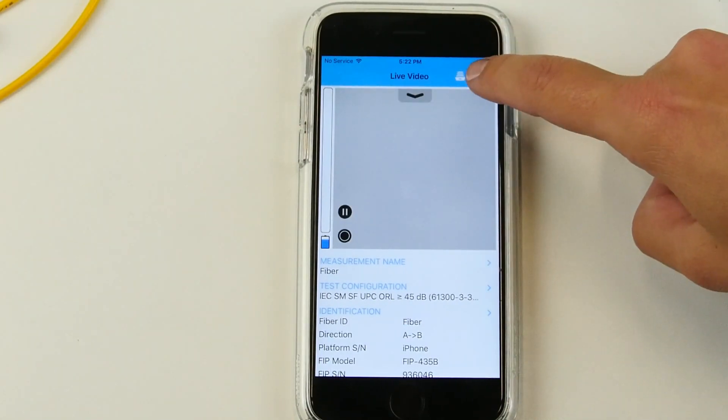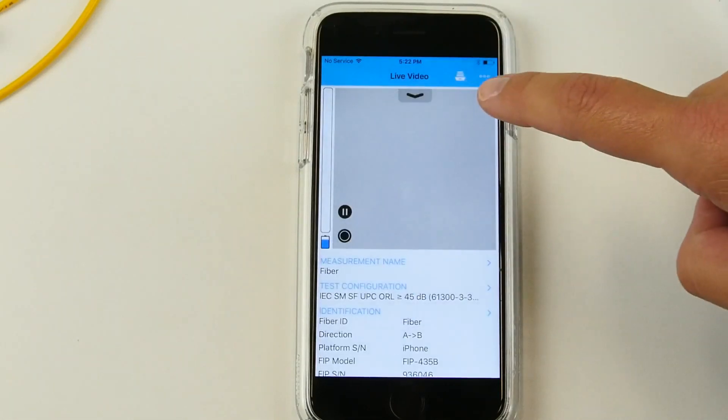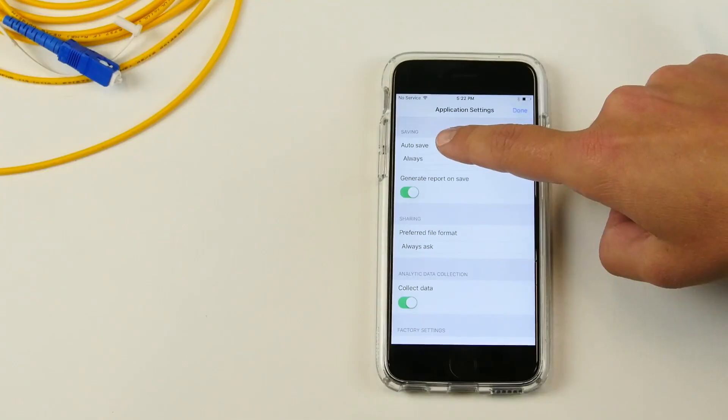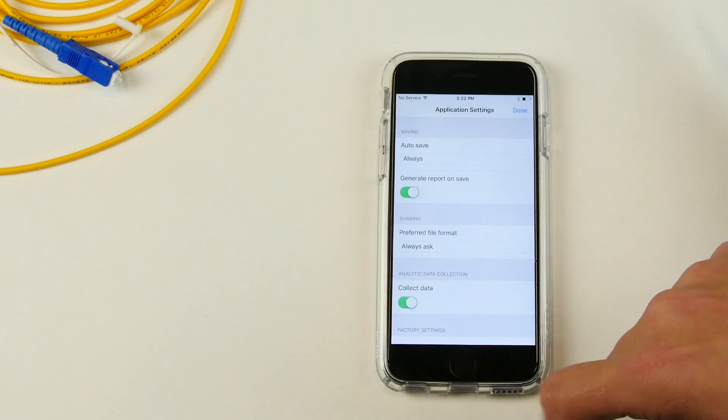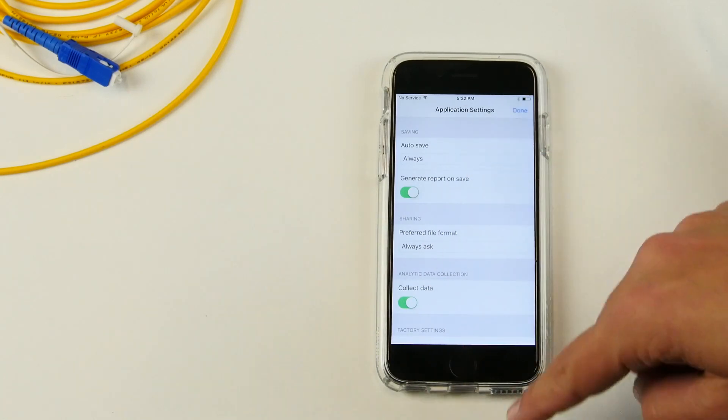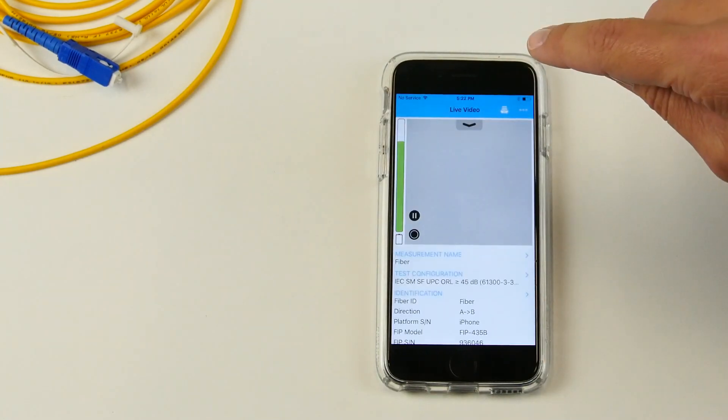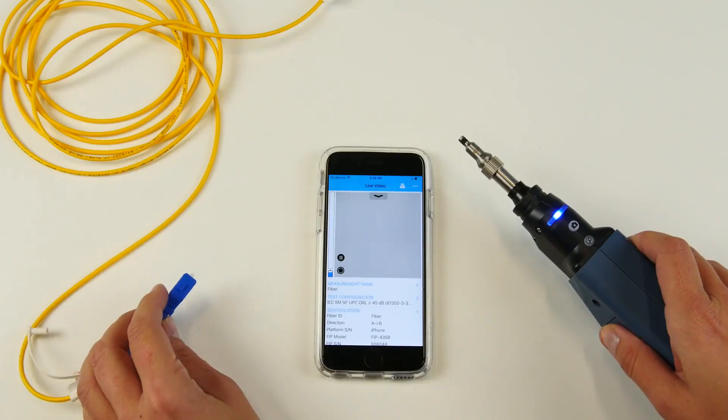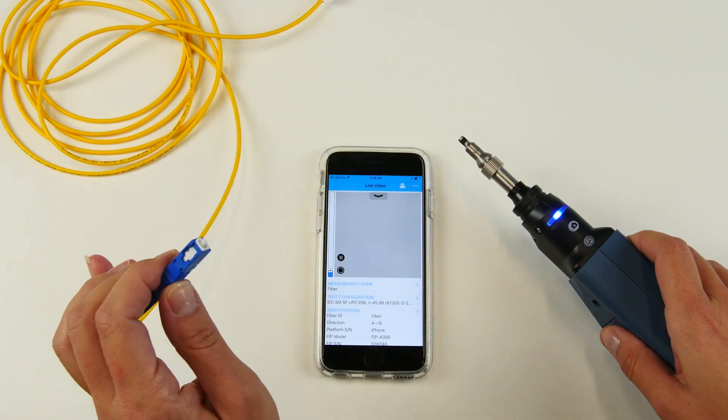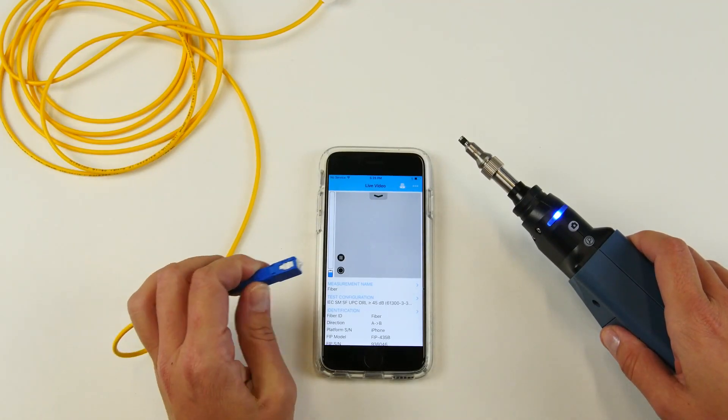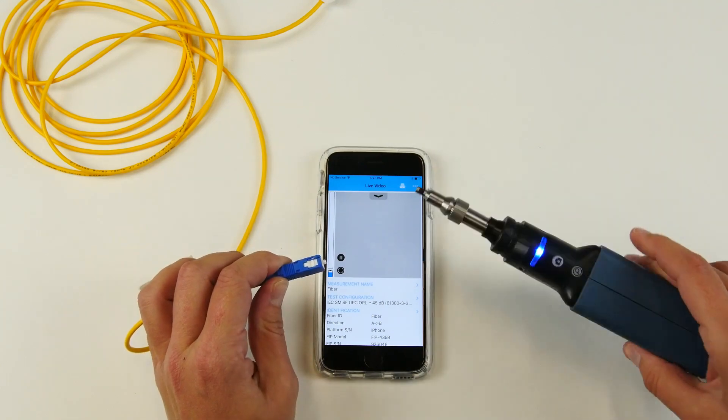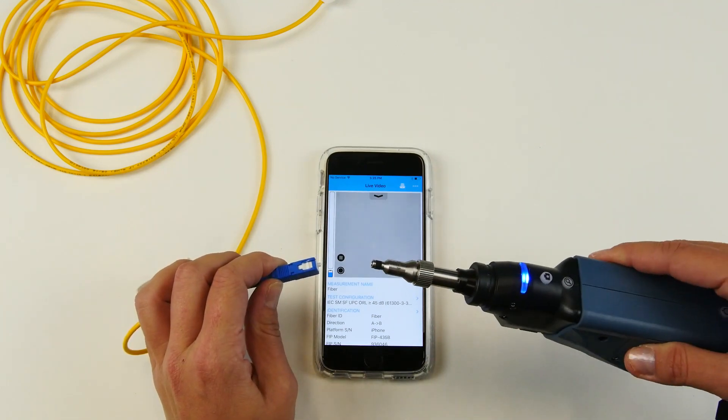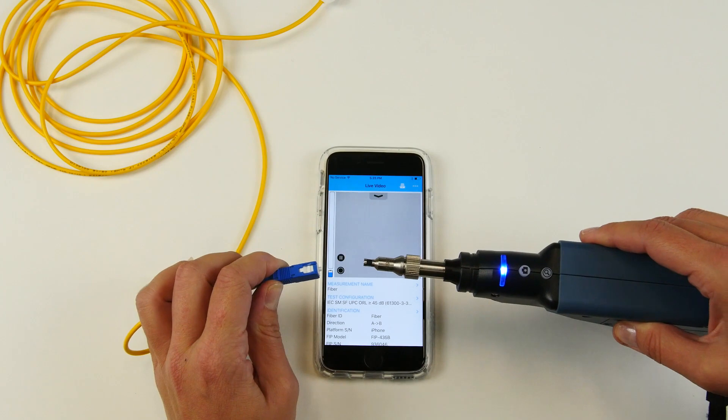You can also go into the application setting and configure if you want to auto-save all of your tests and generate a report as soon as you perform a test. It's now time to test. We're going to test a SC-UPC connector using a U25MB tip, which we're going to cover a little later.